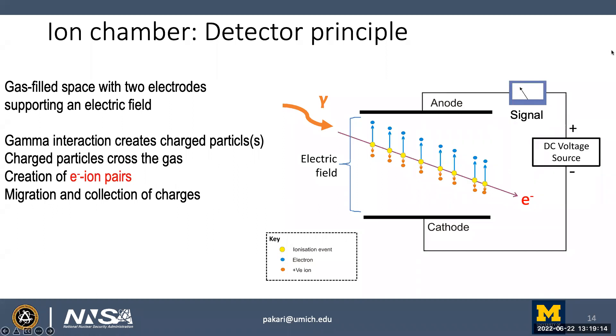The ion chamber: same concept — a gas-filled space with two electrodes and an applied electric field. A simplified apparatus has an anode, cathode, a DC voltage source, and a device to measure current. A gamma ray enters from the left, interacts via the photoelectric effect for example, liberating a high-energy electron that ionizes the gas volume, creating electron-ion pairs. The electrons migrate to the anode and ions to the cathode, producing a measurable signal across a resistive device.